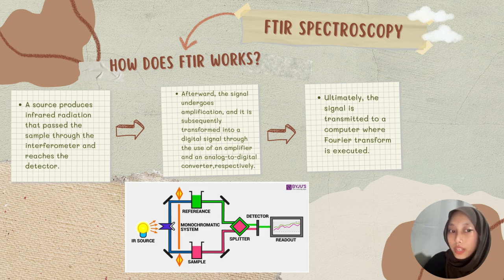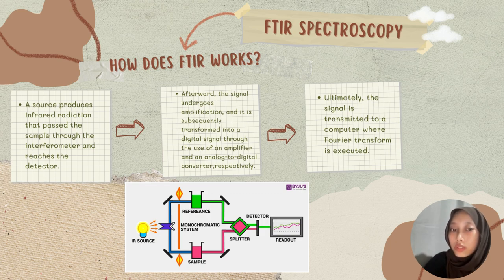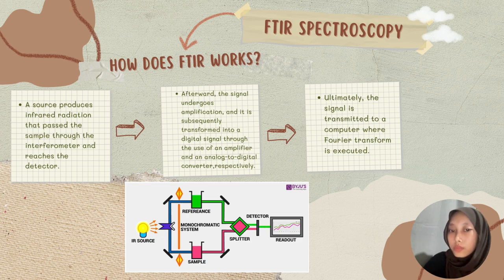How does FTIR work? A source produces infrared radiation that passes through the sample, through the interferometer, and reaches the detector. Afterward, the signal undergoes amplification and is subsequently transformed into a digital signal through the use of an amplifier and an analog-to-digital converter. Ultimately, the signal is transmitted to a computer where the Fourier transform is executed.